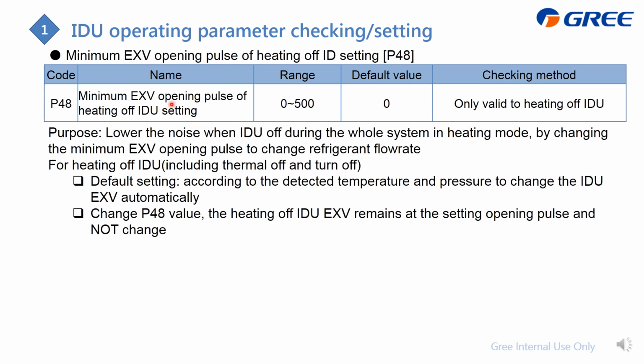This is the minimum EXV, which changes the refrigerant flow rate to improve the noise. For more detail, you can go to my GMV noise troubleshooting video. For this one, the default setting is 0, and if we display 0, it means the change is according to the system control, not by a fixed value. Then you can change this to a fixed value, for example 70.